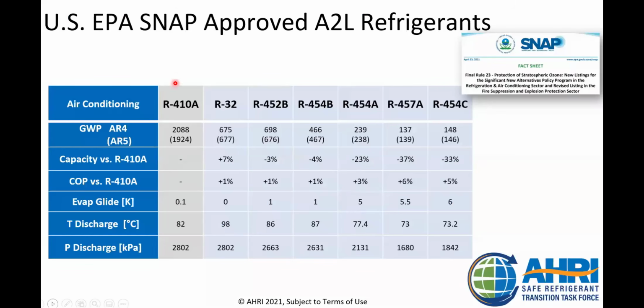Looking at some of these side by side, this is 410, this is 32, this is 454B. We don't care about the other ones right now because nobody's using those for HVAC in the United States, so it doesn't make a difference to us. If you are unaware, any refrigerant with a 400 number, 400 means it's a blend. It's two or three things mixed together, right? So 410A is a blend. 410A is actually 50% R32 and 50% R125, right? R32 is not a blend. It is a single refrigerant. And then all these other ones are also blends, usually with R32 involved in there.